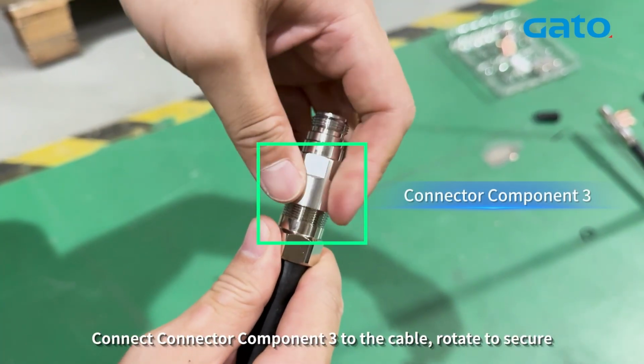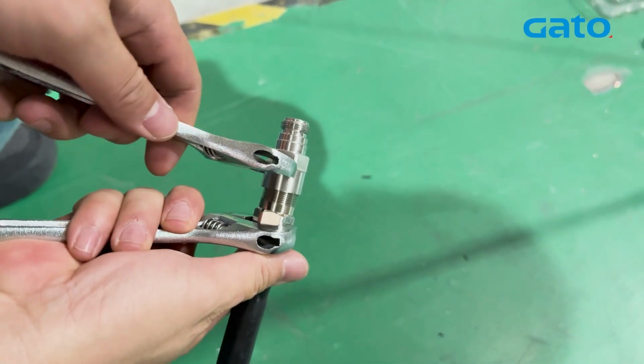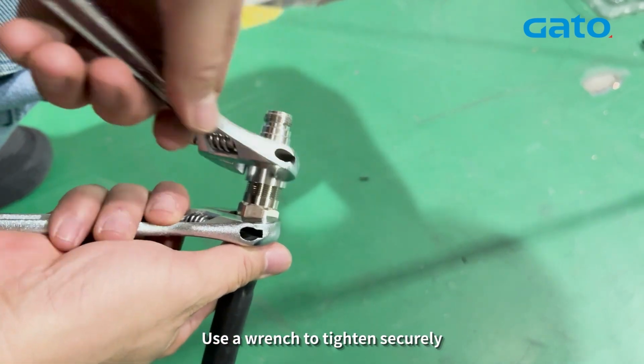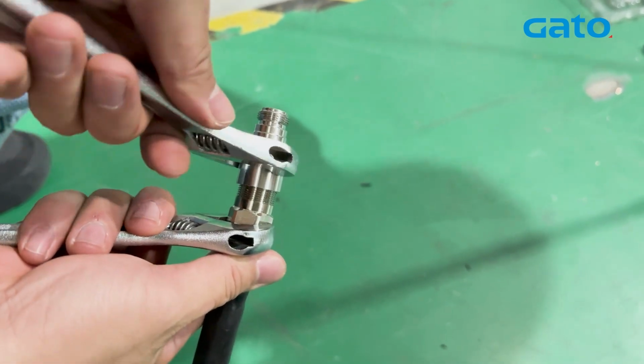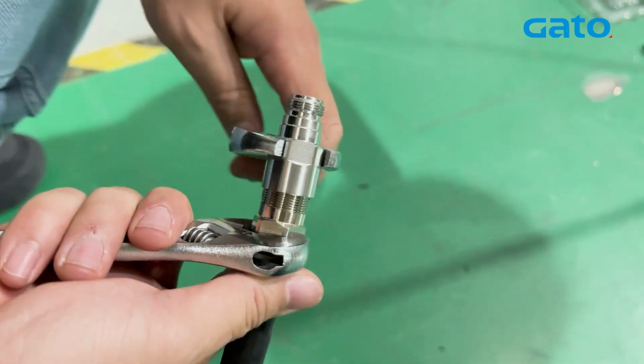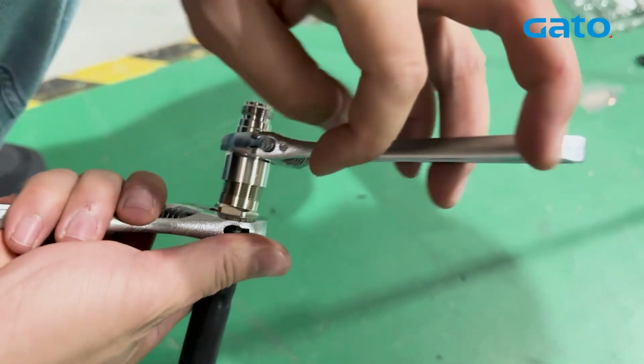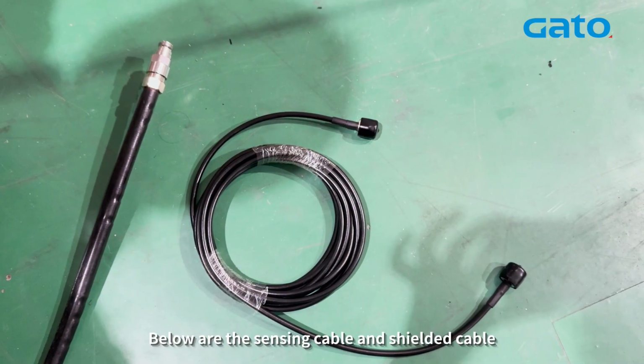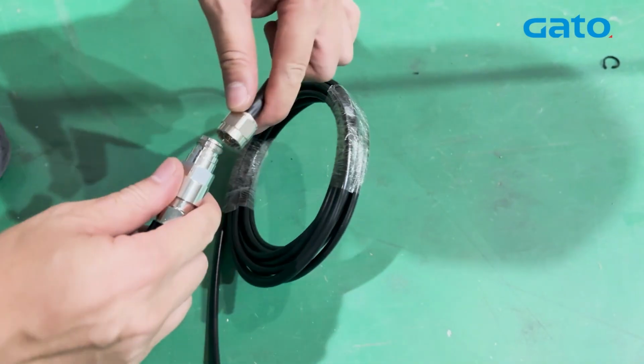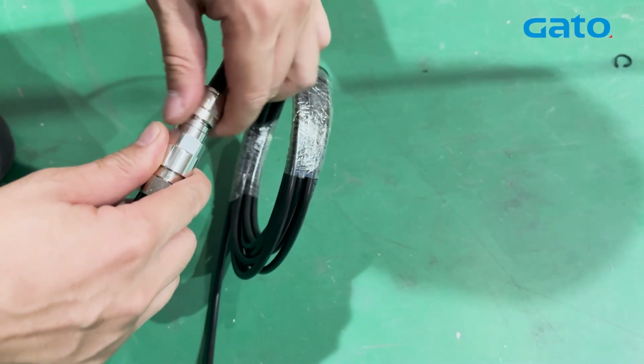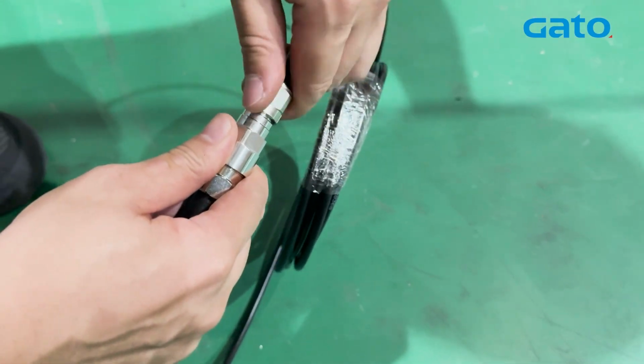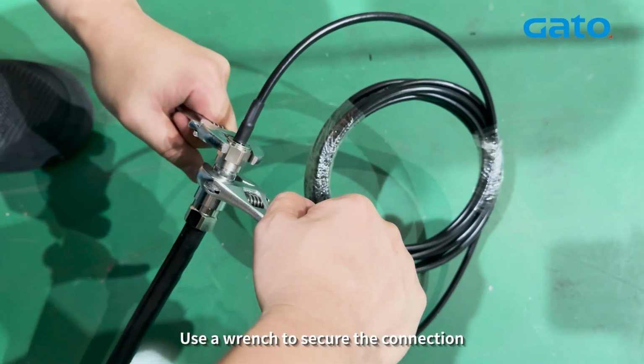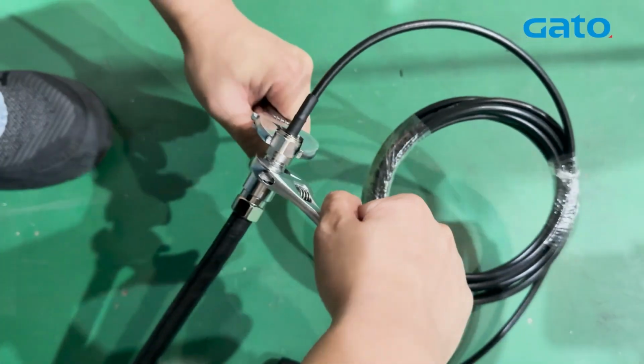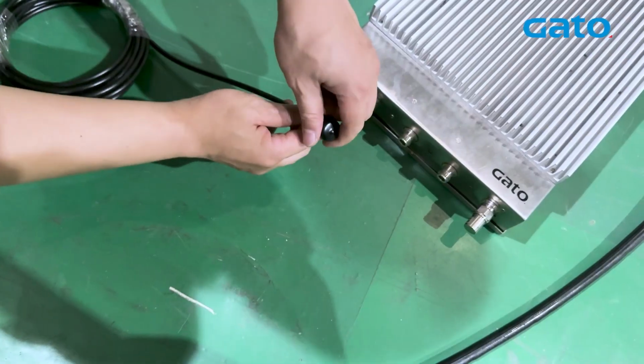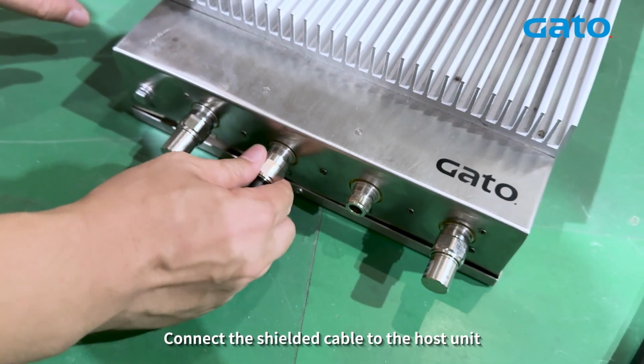Connect connector component 3 to the cable. Rotate to secure. Use a wrench to tighten securely. Below are the sensing cable and shielded cable. Connect the sensing cable to the shielded cable. Use a wrench to secure the connection. Connect the shielded cable to the host unit.